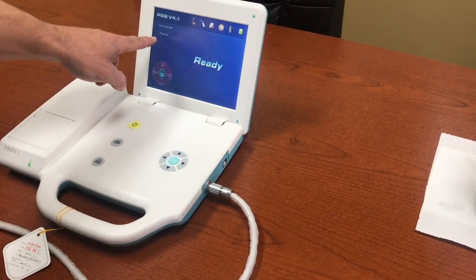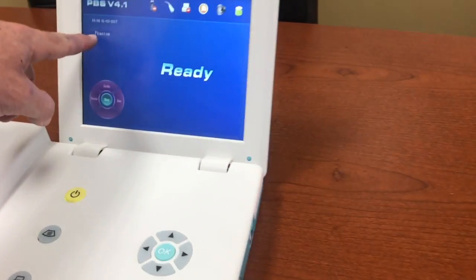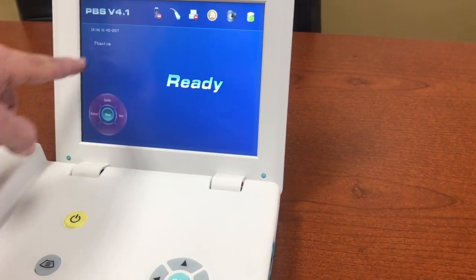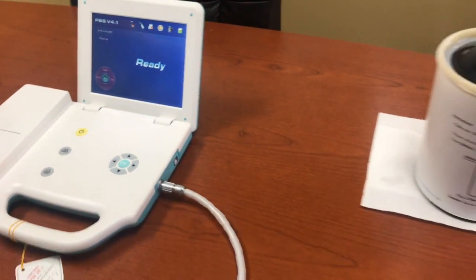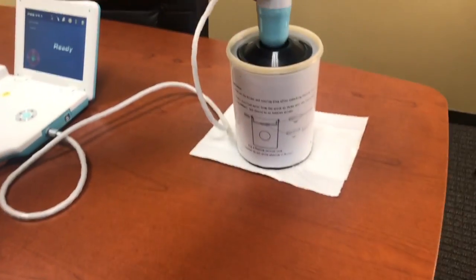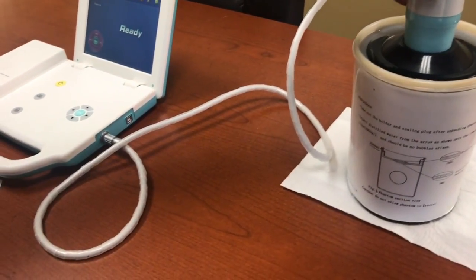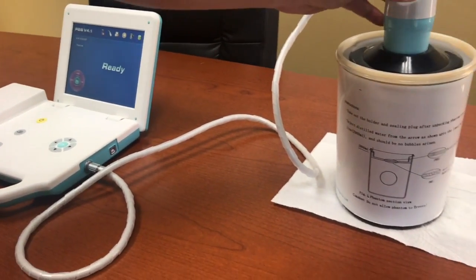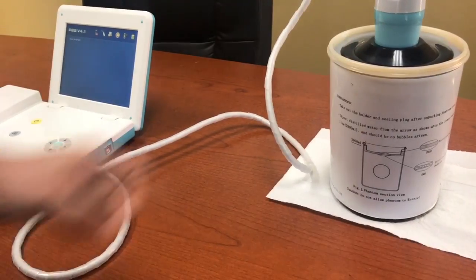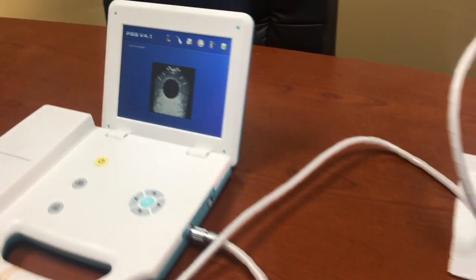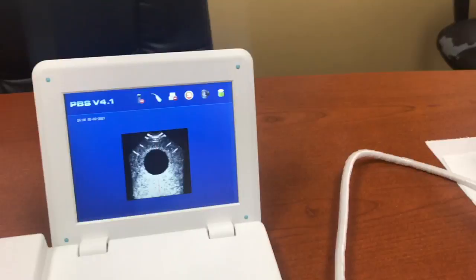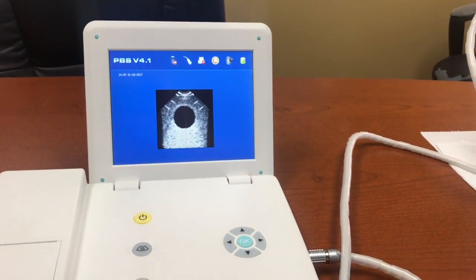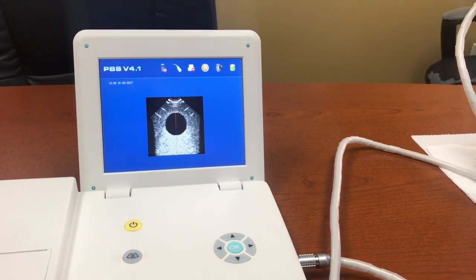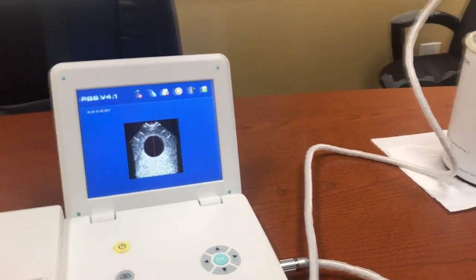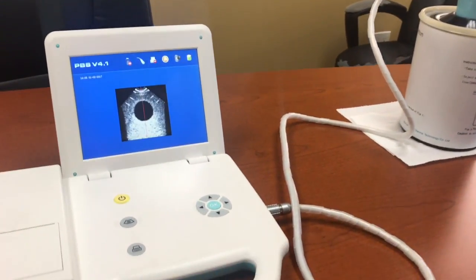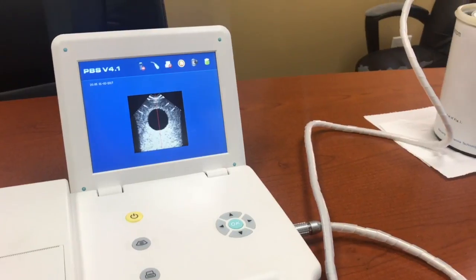At this point, the human icon is replaced simply by the words phantom, and the unit is ready to test. We'll place it into our bladder scanning phantom, which is filled with water at this point, and I'll begin a pre-scan by simply depressing the button. You will see a nice solid image of the bladder. The phantom makes it extremely easy to see what we're doing. We're going to move this so that the center line is on point with the center of the bladder.